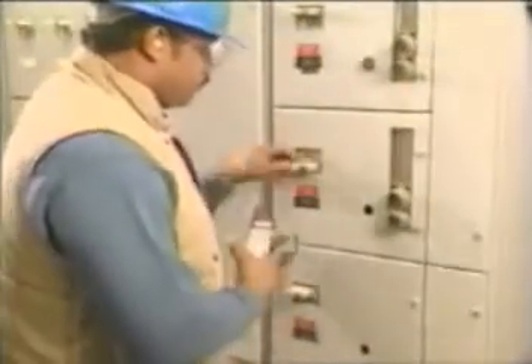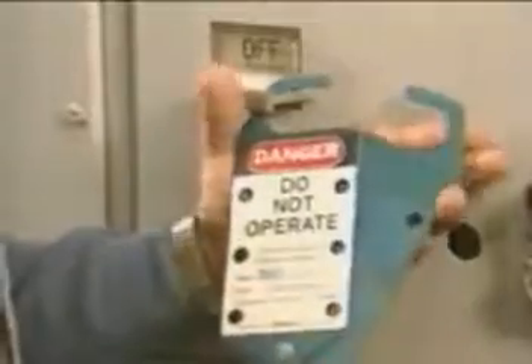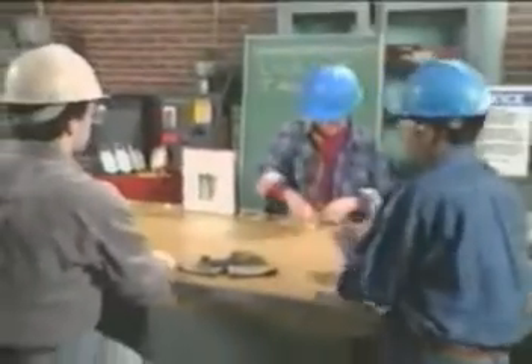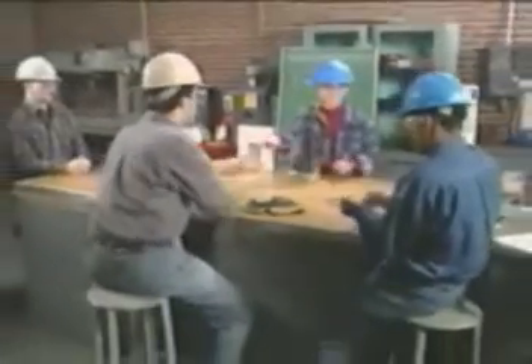As you know, locking out is a technique used to prevent hazardous energy from injuring and even killing workers. In a lockout, a padlock is placed on a disconnect switch, circuit breaker, valve handle, or other energy isolating mechanism that is in the off or closed position. In a tagout, a written warning tag is placed here instead. Your employer will provide all individual locks, keys, tags, and other lockout tagout materials that you will need. These items must be durable, keyed differently, and unable to be removed easily. For example, tags must be made so that when exposed to wet conditions, they will not become illegible. They must not deteriorate in corrosive environments either.